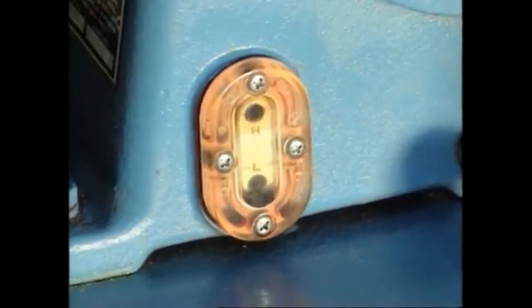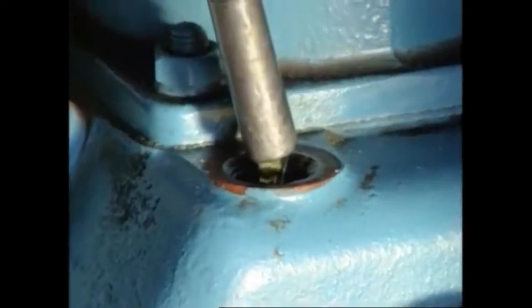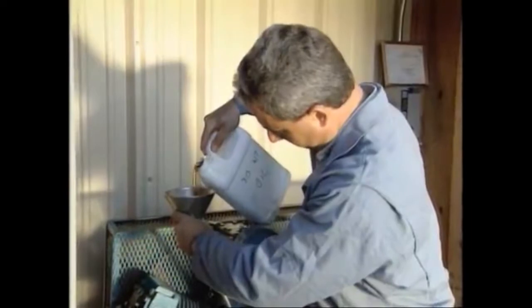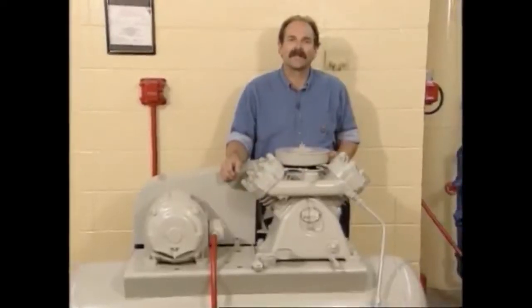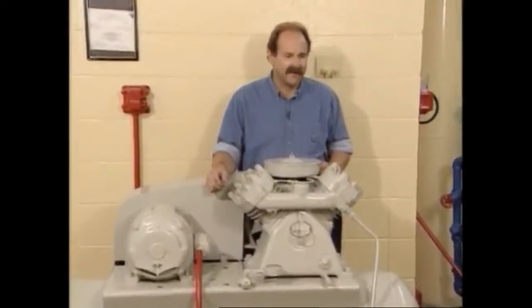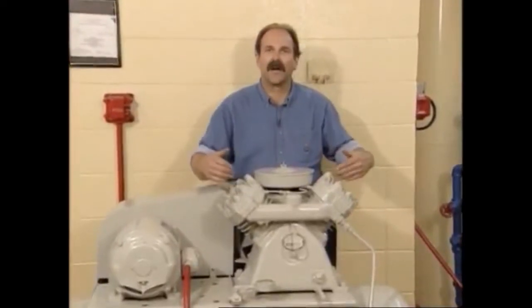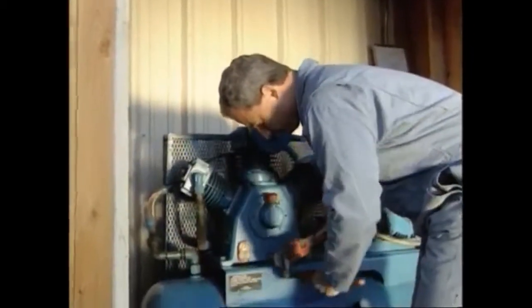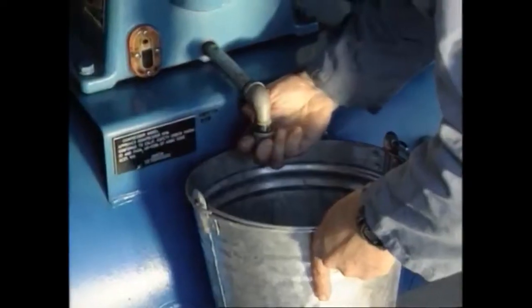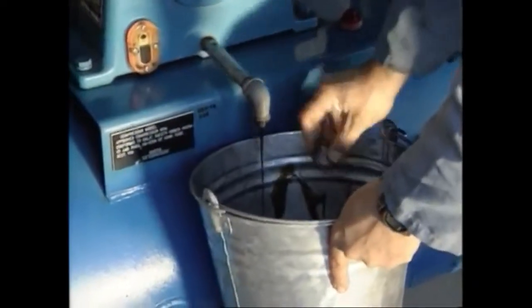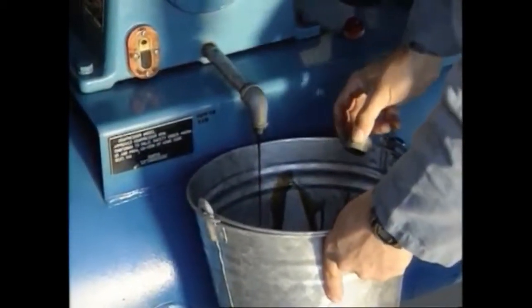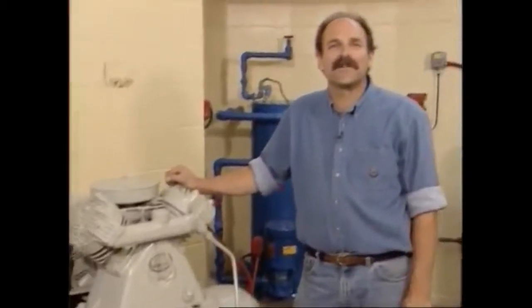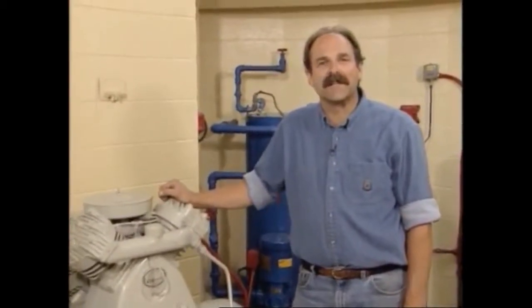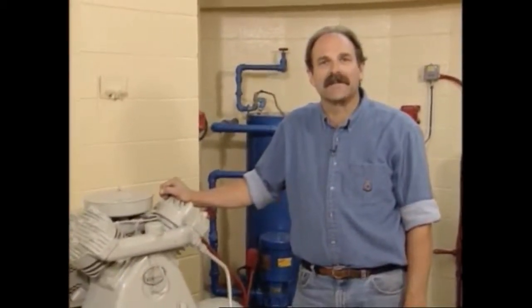On some compressors, it is possible for the oil to get into the compression side and lock up or damage the compressor. When air or gas is compressed, heat is generated, and the compressor becomes very hot. This tends to break down oil faster, so most compressor manufacturers have special oils recommended for their particular compressor. Also, due to the heat and contamination, it is necessary to change oil quite frequently. Compressor oil should be changed every 3 months unless the manufacturer states differently.